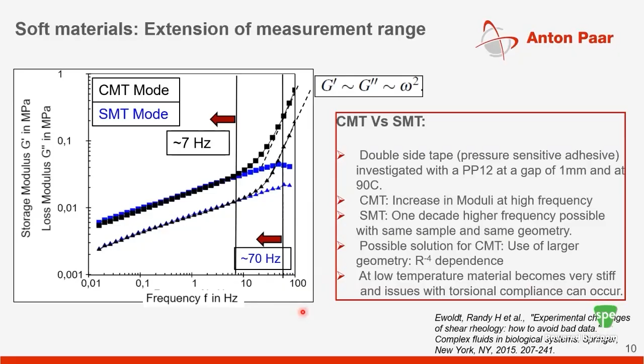Now, if we talked about the CMT and the SMT modes earlier, and if you take a look in the CMT mode, both the torque measurement and the deflection actually is happening on the same side of the device. And in the SMT mode, the application of deflection and the measurement are actually happening on opposite sides, right? You're driving it here and you're measuring from the top transducer. So it's a separated motor transducer type experiment. And if you take a look at the total torque, basically it is a summation of the sample torque plus the acceleration torque.